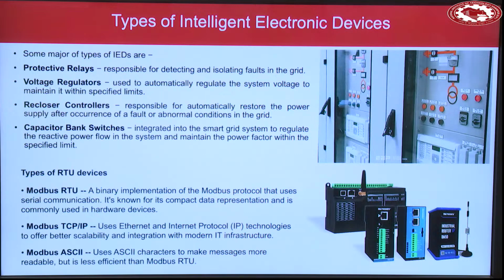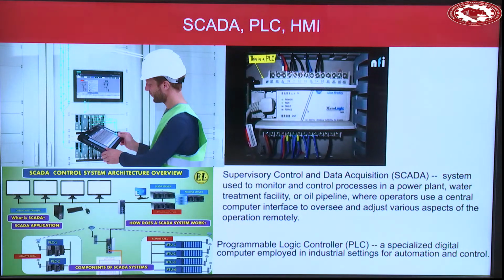And then you've got different RTU devices. Remote terminal units are the ones that send data from your substation to the control center. So all substations need to send data to the control center so that I can see the state of my system. Now these devices run different protocols, Modbus is one of them, I'll talk about it in a minute. Then you've got PLC. What is a PLC?